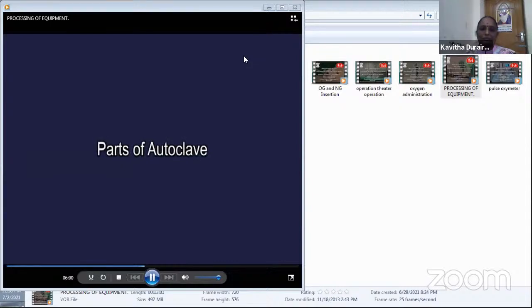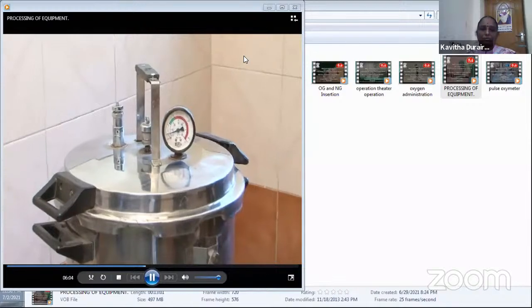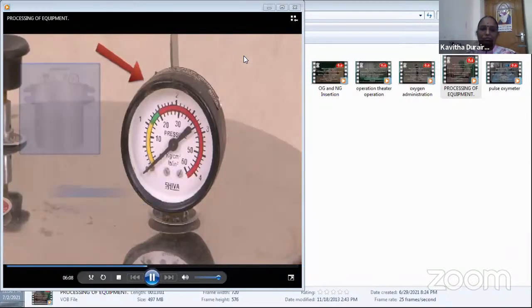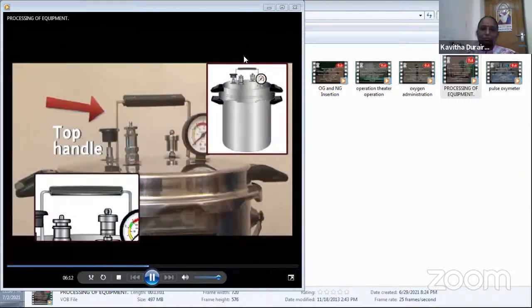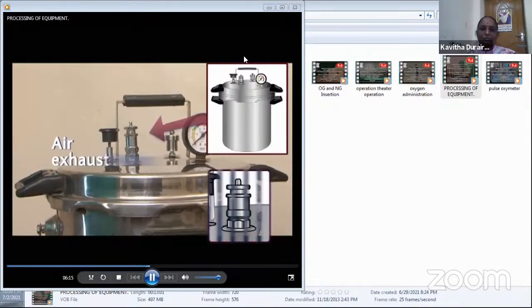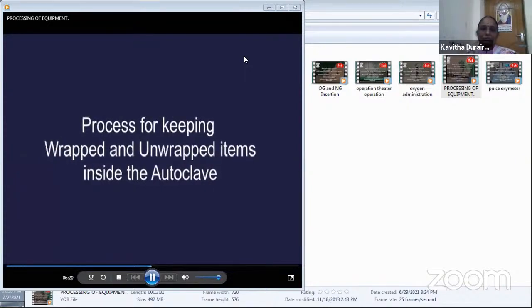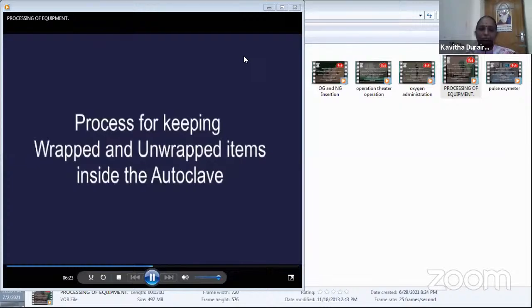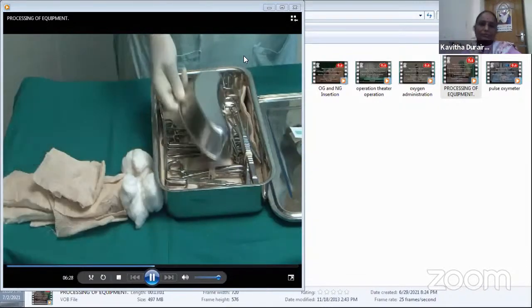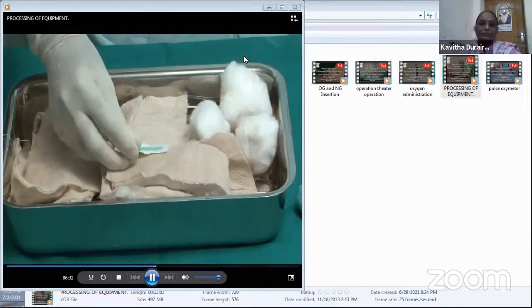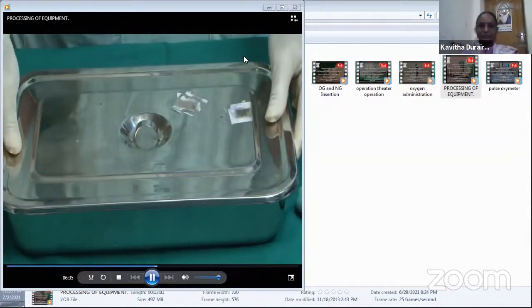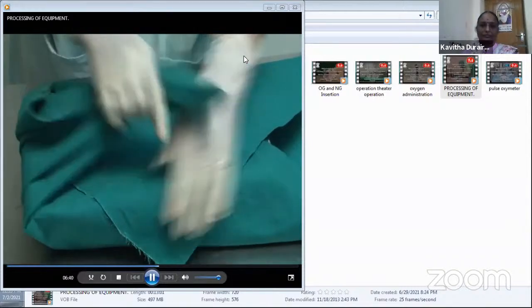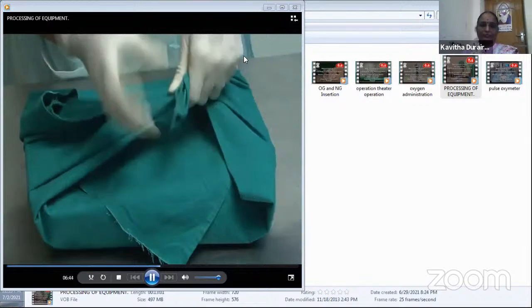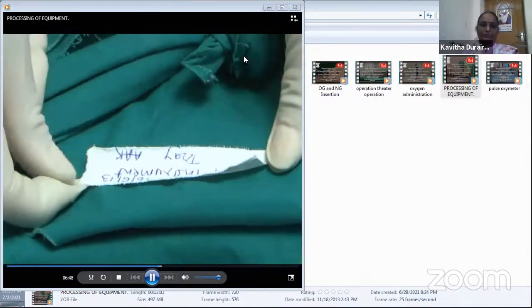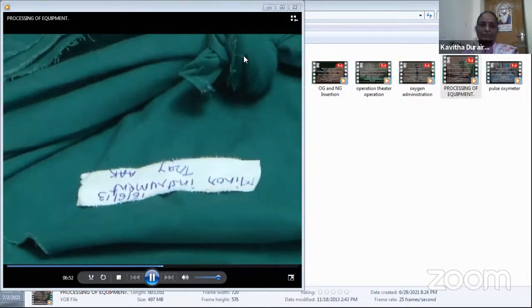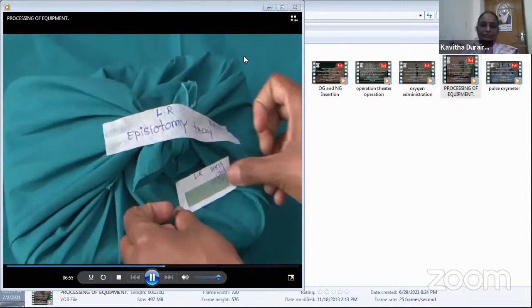Parts of the autoclave: geared steam gauge, excess pressure relief valve, top handle, control valve, air exhaust tube. The process for keeping wrapped and unwrapped items inside the autoclave: surgical equipment and drapes are to be put into an adequate size tray. Keep the indicator strip and wrap it. Seal it with adhesive tape after putting the date and signature.